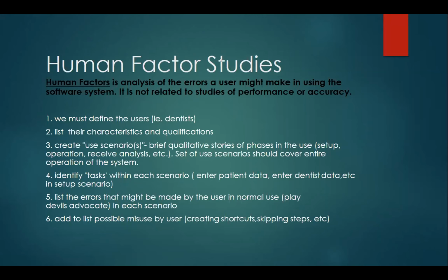It looks to address the human factors. You want to conduct a hazard analysis on these errors. You want to mitigate these potential hazards, and the human factor validation will be an observed test following protocols, with 15 dentists, FDA required, using the system. Each scenario will have a protocol. The test protocol must include all the identified possible errors that the observer will be looking for. Each participant will be interviewed following the test of a scenario about his experience. Those possible errors will be touched on. Participants may uncover these errors, and a report should be written.